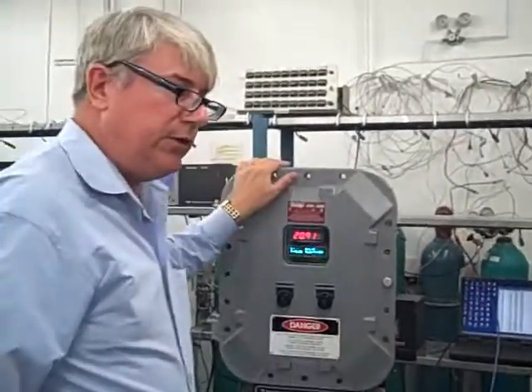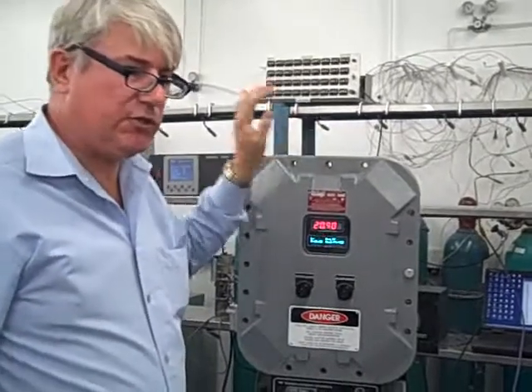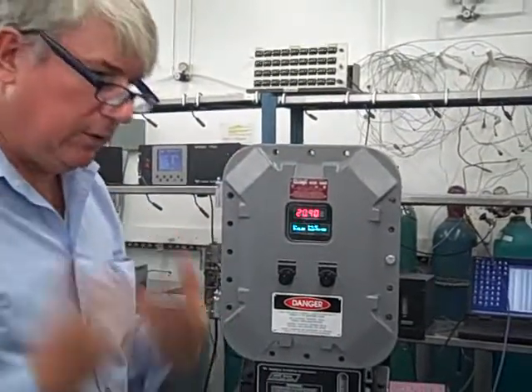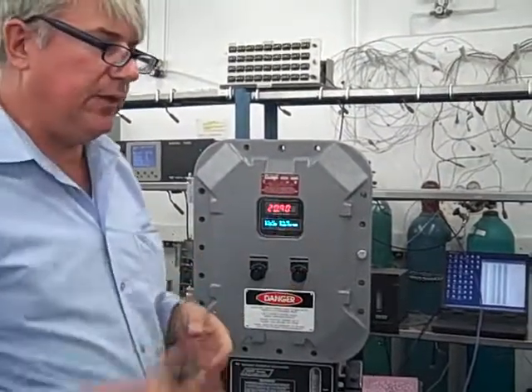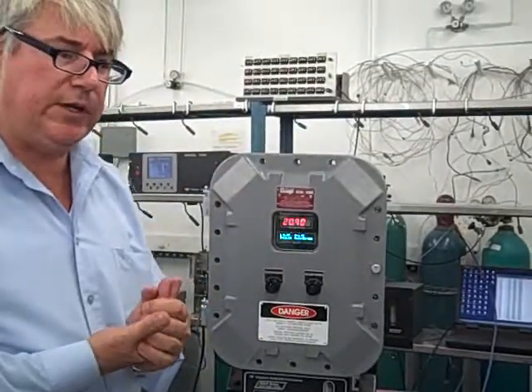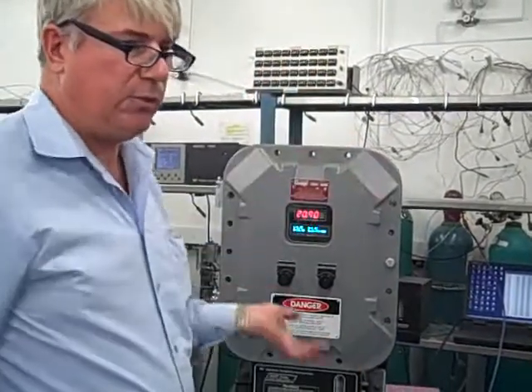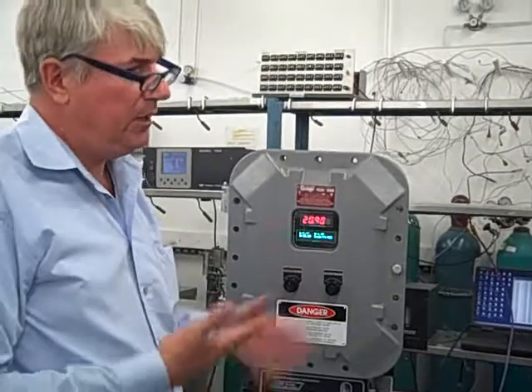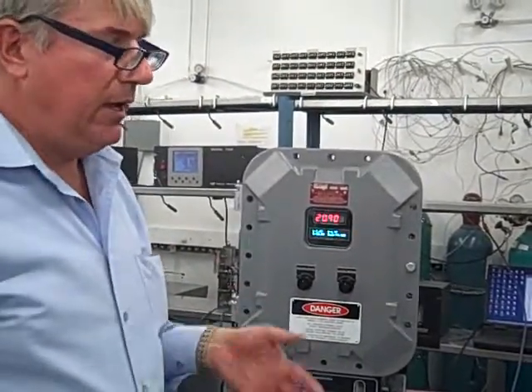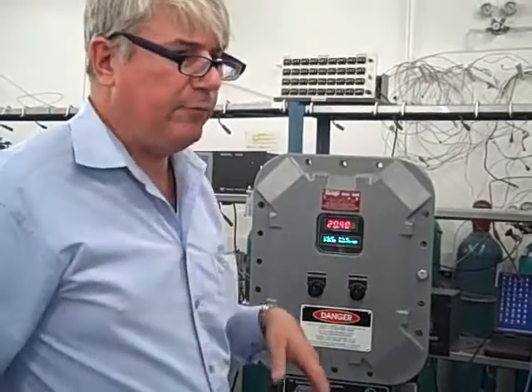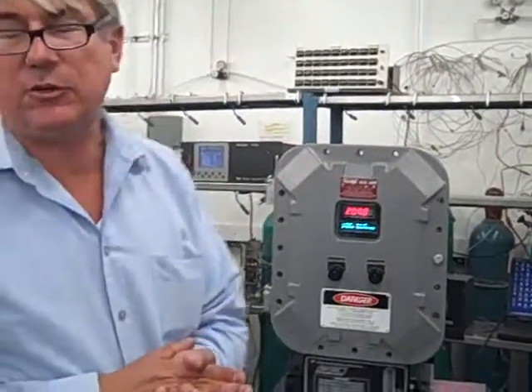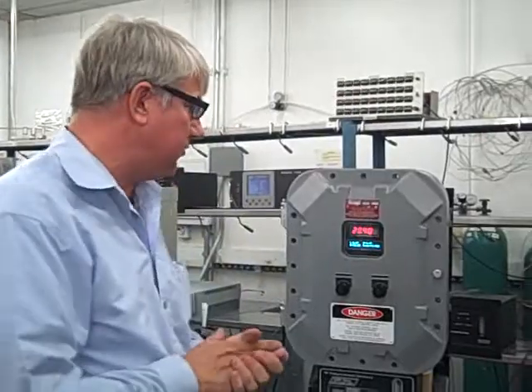What you'll see with the trace oxygen sensor is it will last typically 6 months to a year, and then suddenly over the course of a day its output will go high. So you may be reading a half a ppm for many months on your process, and all of a sudden you come in one day later and it's reading, say, 1.5 ppm or 2. In many cases, that is the sensor has expired. It's time to exchange the sensor. That's how most of our customers know how to change the sensor.